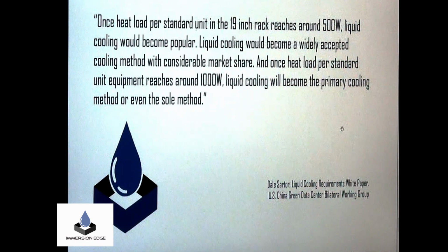The quote is: once heat load per standard unit in the 19-inch rack reaches around 500 watts, liquid cooling will become popular, a widely accepted cooling method with a considerable market share. Once heat load per standard equipment reaches around 1,000 watts, liquid cooling will become the primary cooling method, or even the sole method. I know that's going to be a little bit of opening for debate, but we understand there's going to be a certain point where we know we're there now. I'm really thrilled that he actually said that, and had a chance to chat with him about it. I can send you that white paper as well if you're interested.